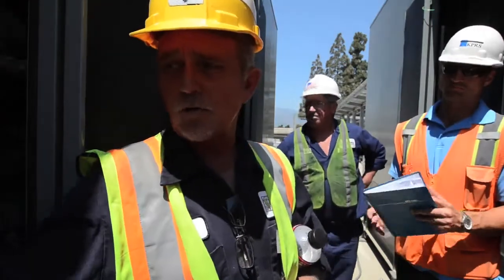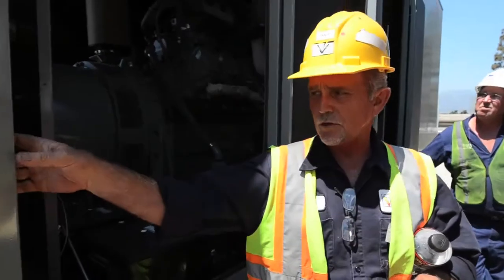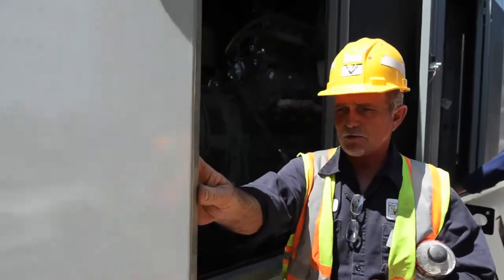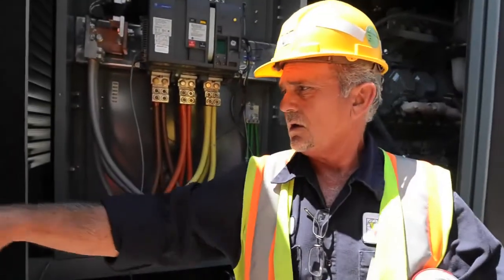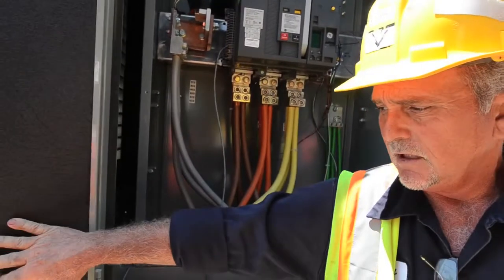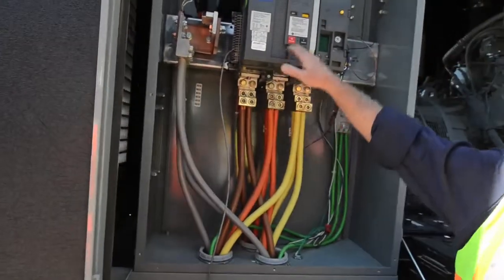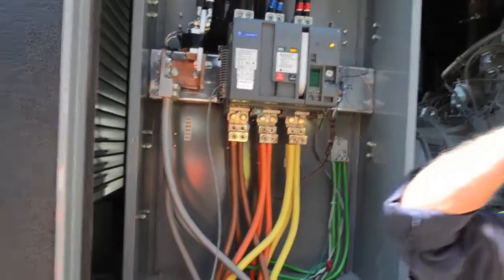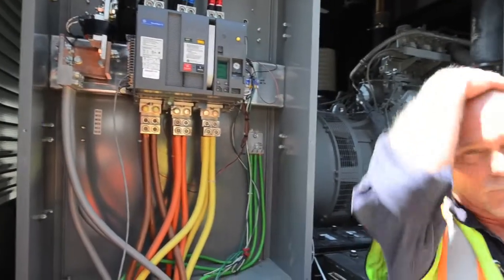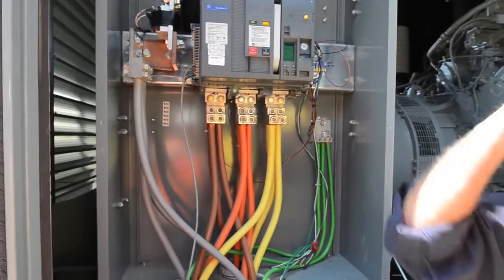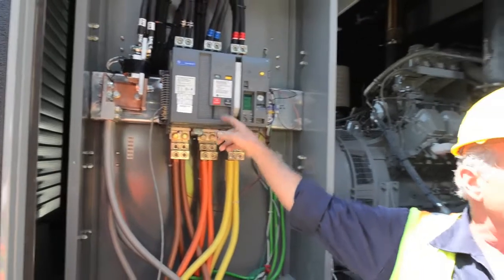Now if I come in behind this door panel right here, let's open this one up. This will have a permanent cover over it. It will be bolted on. And this is the main circuit breaker. This is the one that I'm telling you that you don't ever come out and you don't mess with. You don't push it, you don't do anything with it. When I leave here, I will install a cover over this.